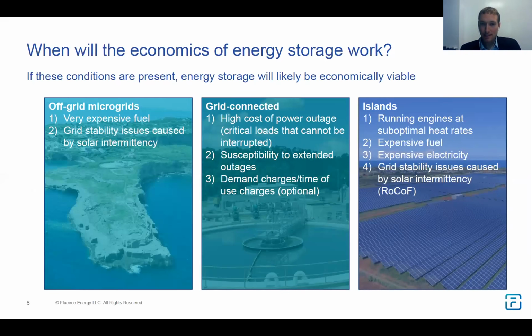For grid connected systems, the key is if there's an extremely high cost of a power outage, like the water treatment plant I mentioned, where they'd be discharging millions of gallons of sewage. If that cost is very high, you can't afford to not have a plan B.